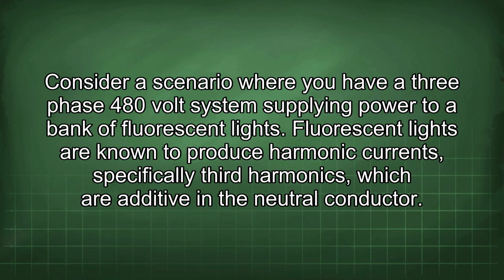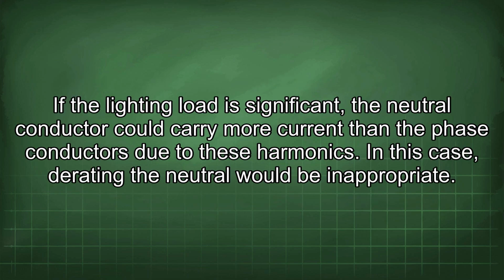Consider a scenario where you have a 3-phase 480-volt system supplying power to a bank of fluorescent lights. Fluorescent lights are known to produce harmonic currents, specifically third harmonics, which are additive in the neutral conductor. If the lighting load is significant, the neutral conductor could carry more current than the phase conductors due to these harmonics. In this case, derating the neutral would be inappropriate.